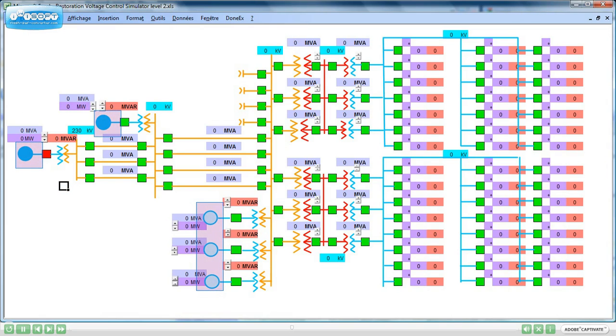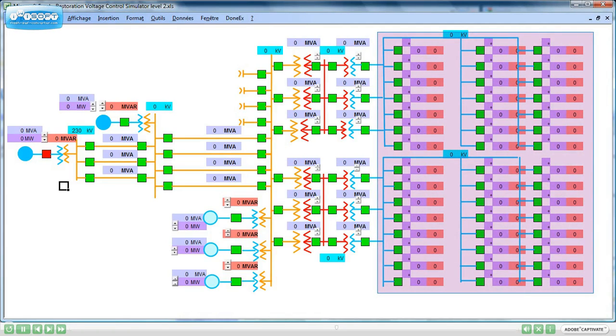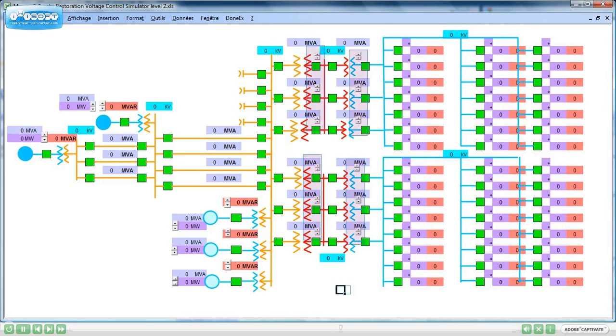There are 5 power plants. The first power plant on the left middle is set at 0% speed droop, and there is a wheel to increase or decrease the megavars. For the other plants the megawatts and the megavars can be adjusted using wheels. There are lots of 230 kV lines, 230 to 138 kV transformers in parallel, and in series with these transformers 138 to 25 kV transformers, and then 25 kV buses with lots of 25 kV feeders. All transformers are equipped with load tap changers. All the feeders are with cold load characteristics.